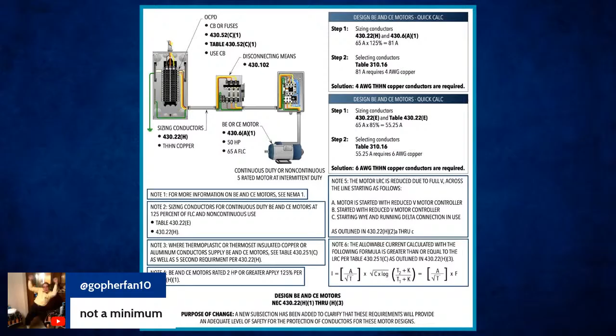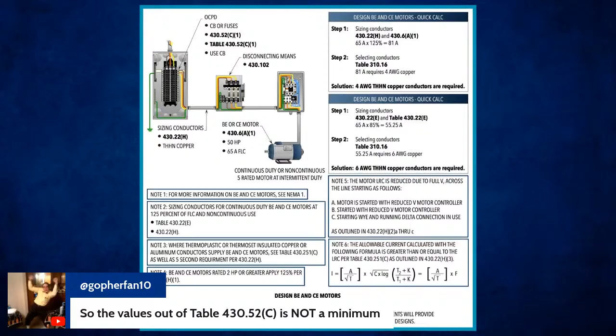Now, the next one I'm going to do is the maximum size. I'm doing an inverse time circuit breaker. I didn't exceed 100 amps for my motor, so I'm going to be able to take this at 400%. But one thing I want to point out, everybody, if you go look at Table 430.52(C)(1), this is interesting because you know what the heading says there? Maximum rating or setting. Well, this is the maximum rating or setting for your starting point at 250%. You will not exceed this percentage. This is the maximum percentage you can use in this table. We started with 65 amps at 250%, and I started with a minimum size, then I went to the next size.